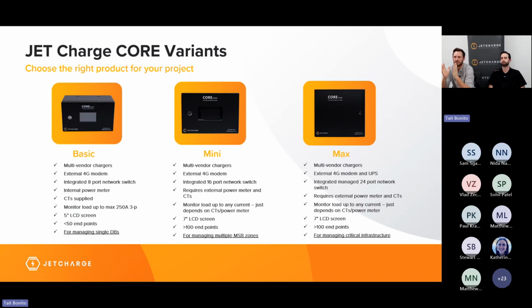Core Basic is for situations where you only need to control the EV charging load within one circuit breaker or supply point. It comes with an inbuilt power meter and suitable CTs. Because of this, Core Basic is only suitable for monitoring loads of up to 250 amps on 3-phase.